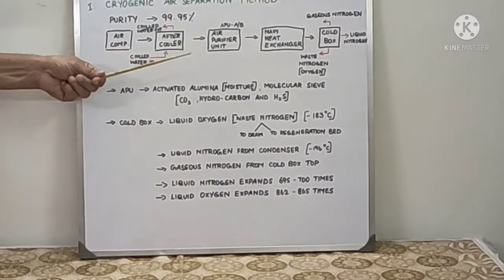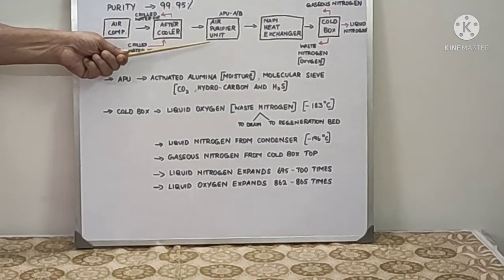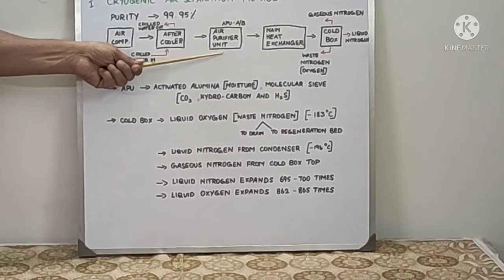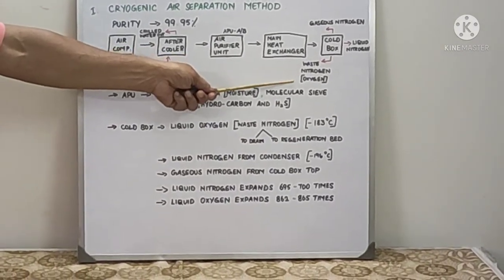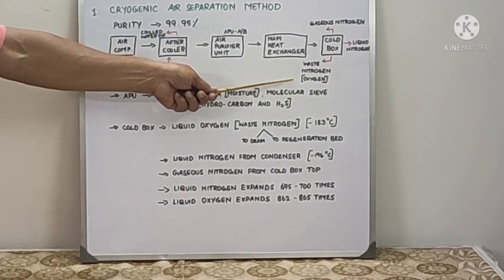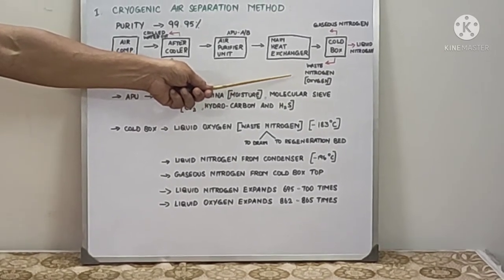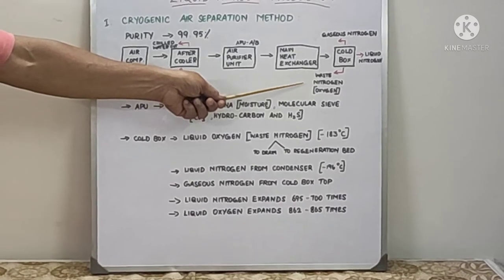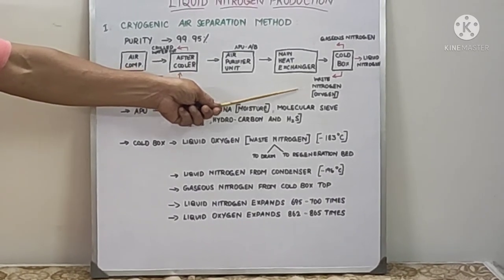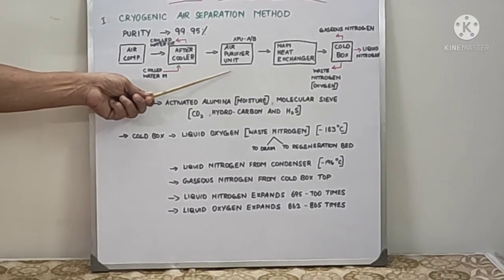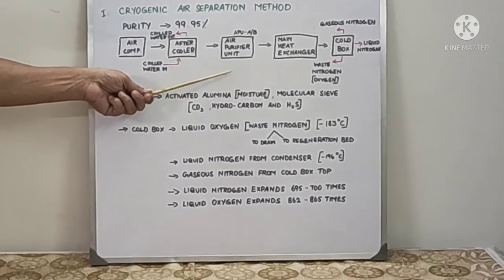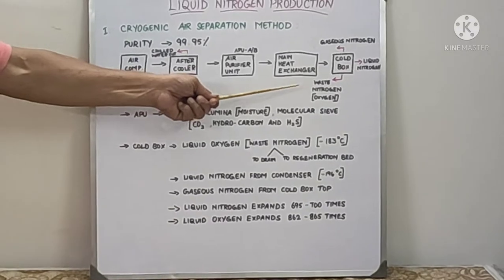In the air purifier unit, normally we will have two sets of units. One will be in service and the other will be in regeneration. The waste nitrogen that is rich in oxygen will be normally vented out by timer through the vaporizer. One line is routed to the air purifier via electric heater. The regenerated bed is regenerated by means of the waste nitrogen after getting heated.